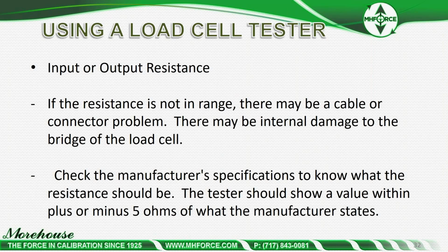If the resistance is not in range, there may be a cable or connector problem. There may be internal damage to the bridge of the load cell. This is the point where, if there is internal damage, if you're lucky, it's just a solder joint. If you're unlucky, the load cell's been overloaded and something's happened. Check the manufacturer's specifications to know what the resistance should be. The tester should show a value within plus or minus 5 ohms of what the manufacturer states.